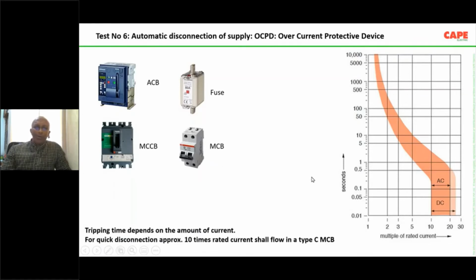Now, one of the first jobs of the standard is to declare the time within which the automatic disconnection should be carried out. Say, for example, in a normal case, something about here where my cursor is moving, I will put it on the pen. So somewhere here, within this particular time, the MCB is supposed to trip in order to achieve safety. This time means something about, let us say, 0.17 second in case of a 230 volt supply.